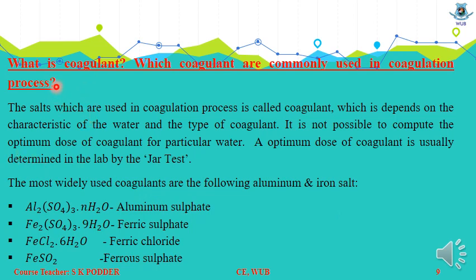The salt used in the coagulation process is called a coagulant. It is not possible to compute the optimum dose of coagulant for particular water analytically; it is usually determined in the lab by the jar test. The most widely used coagulants are aluminum and iron salts: aluminum sulfate, ferric sulfate, and ferric chloride.